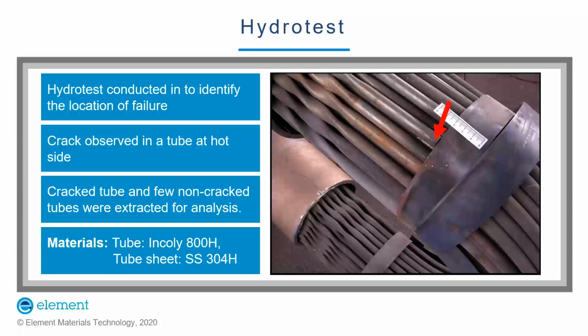This particular cracked tube, which from now on in this presentation will be called the failed tube, was extracted along with a few other non-failed tubes. These tubes were examined for establishing the root cause of this failure. As mentioned before, the material of the tube was Incoloy 800H, which is an alloy used for high temperature application.